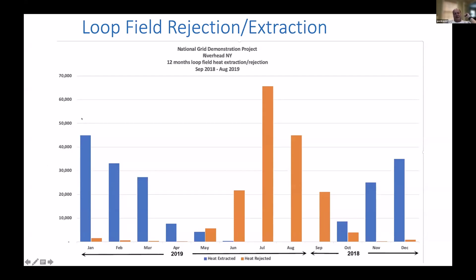And you can see here, this is the amount of heat coming out of the loop field. January, February, March, a lesser amount every month. But this is really pulling heat out of the loop field, almost putting none of the heat in. That switches around May when this neighborhood starts to go into cooling mode. But look how much bigger the energy is being rejected into the loop field.